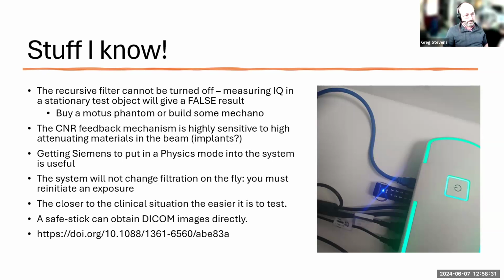It just makes life a little easier because then you've got one less parameter to deal with. The other thing is that the system does not change filtration on the fly. So if you put your foot on the pedal and the system wants to change the amount of copper in the beam, it will only do so on the next exposure. Just bear that in mind, because we ended up getting all sorts of weird numbers and nothing was consistent, and that was one of the main reasons for that.